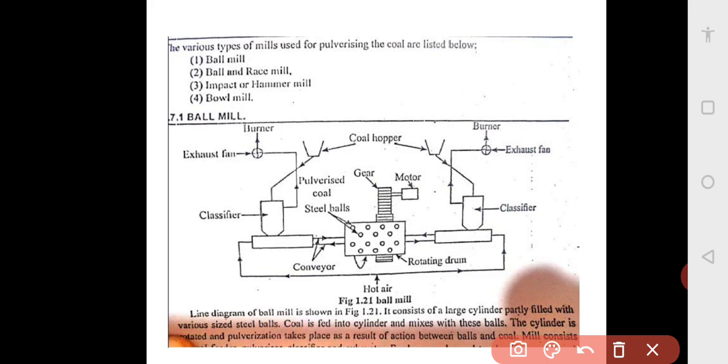Second, there is a considerable quantity of coal in the mill which acts as a reservoir. This rotating drum and balls are big, so the coal in the ball mill acts like a reservoir. This pulverizer prevents fire from going out when there is slight interruption in fuel feed caused by coal clogging in the bunker. If there is clogging, it can continue for some time because there is coal inside the rotating drum.